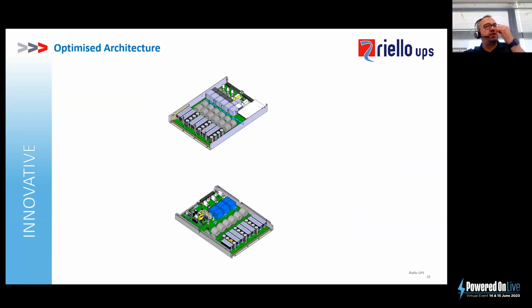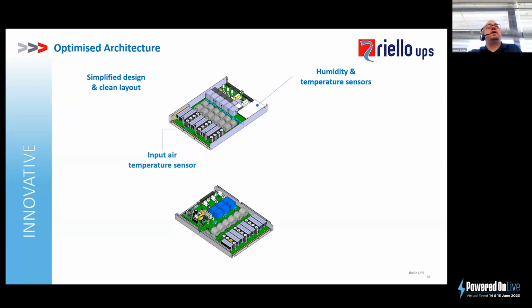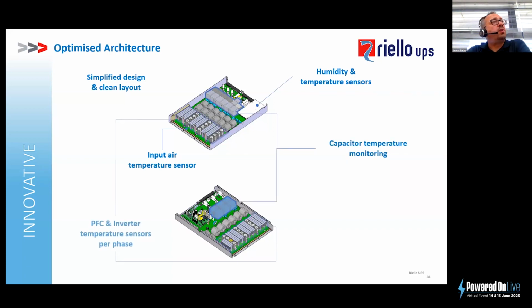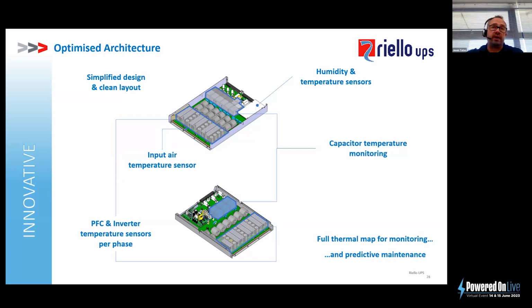Now, it's not just the efficiency that we've looked at. We obviously have to look at the sustainability of the modules, and obviously the way we construct them. So what's happened here is we provided a much cleaner, simplified design layout of the actual module itself. We provided special humidity and temperature sensing. We have put in input air temperature sensing. We have added capacitor temperature monitoring. We have added PFC and inverter temperature sensors per phase. Now, one of the benefits of this is it gives us a full thermal map for monitoring and predictive maintenance. So again, we can plan exactly how the module is going to perform over its lifespan.